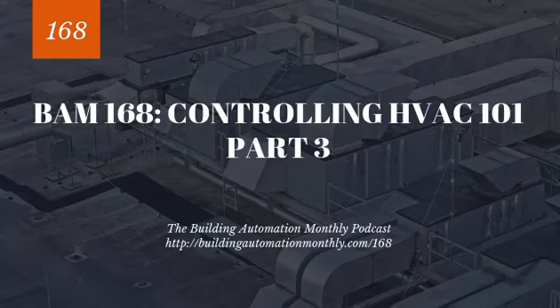And now you get into this scenario, though, where you hit this 30%. And running a centrifugal chiller at 30% or below is really inefficient. And this brings in partial load chillers. Now, these are typically chillers that have multiple stages built within them. You'll typically see this maybe in an air-cooled chiller that's sitting outside, and this will handle smaller tonnage.